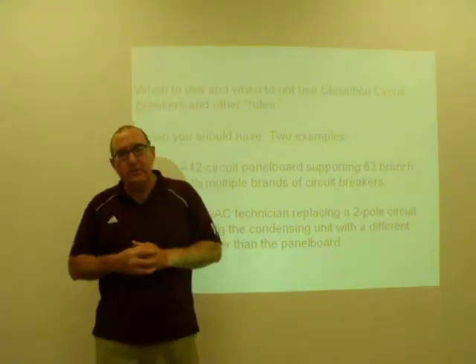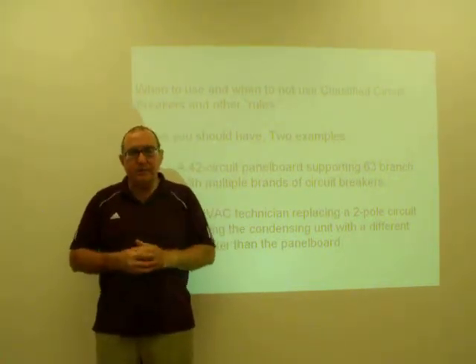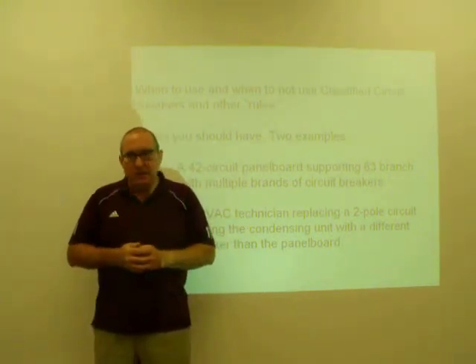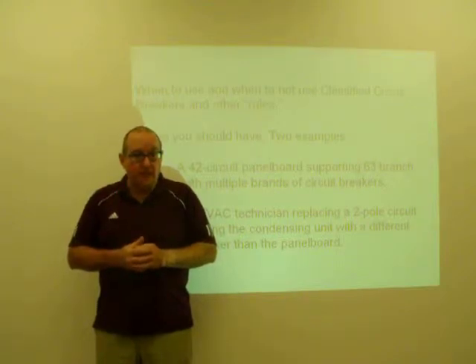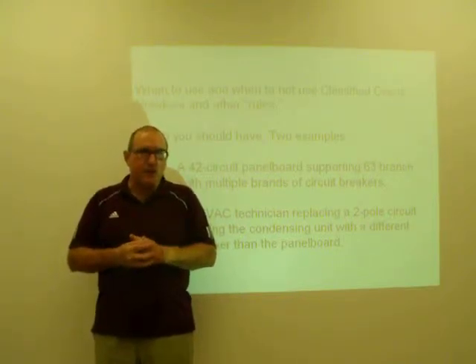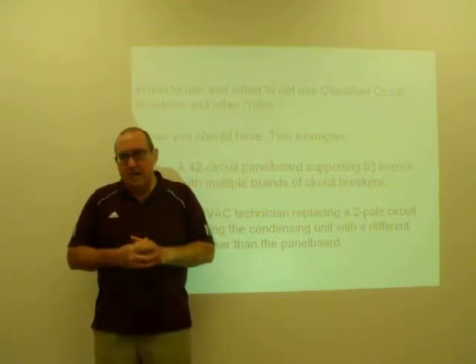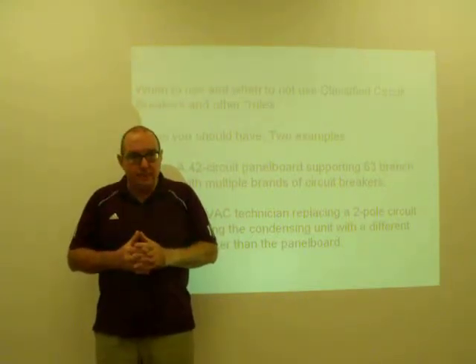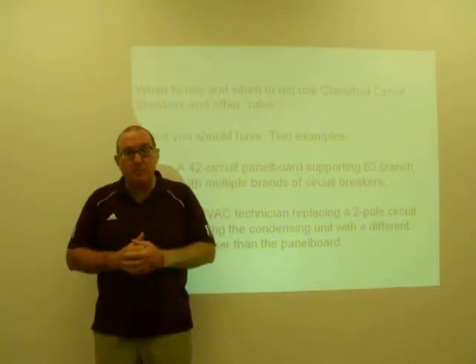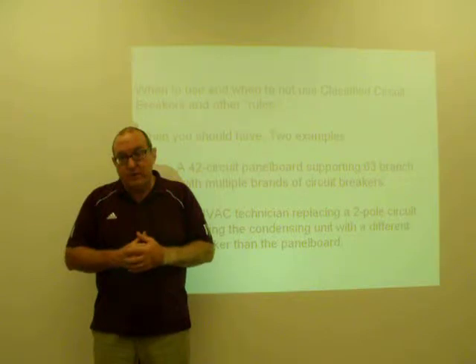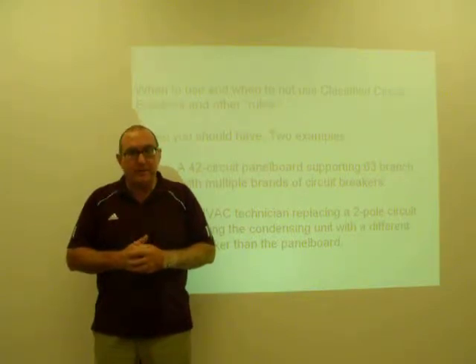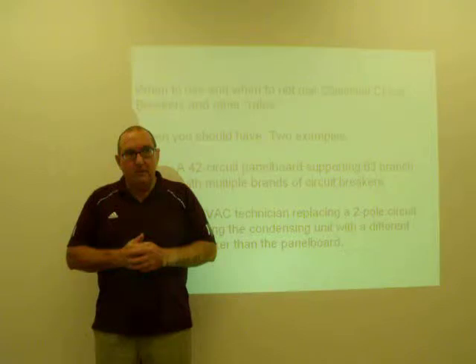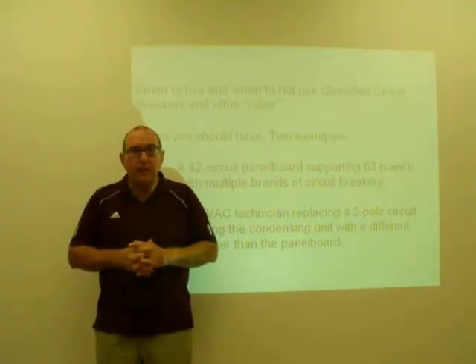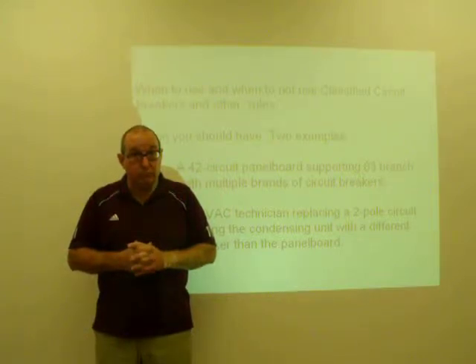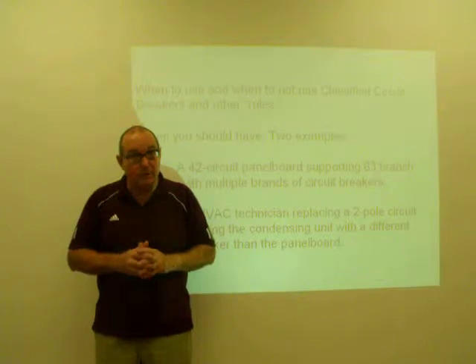When to use and when not to use classified circuit breakers and some of the other rules that are in the National Electrical Code, I'm going to use two examples from personal experience. The first example is a sports bar where I was called to do some electrical work. There I was presented with a 42 circuit panel board that had 63 operating branch circuit breakers and branch circuits, well, breakers as well. And there were a variety of brands of breakers installed in this panel board. And I'll tell you up front, none of them were in compliance with the code.